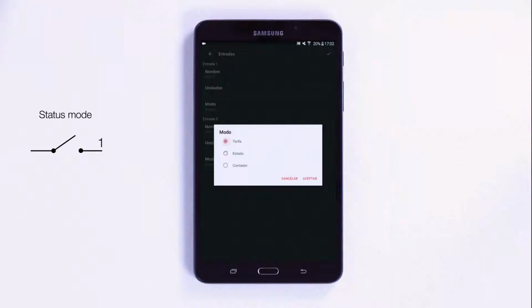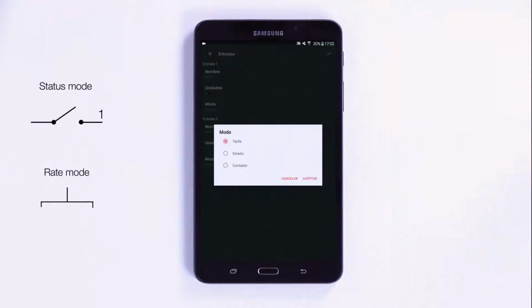In tariff mode, the unit can distinguish between two different tariffs for energy values. So if the installation has a system with a dual power source, e.g. mains and generator, the unit will divide the consumption into two different records to distinguish between the price of both energy sources.